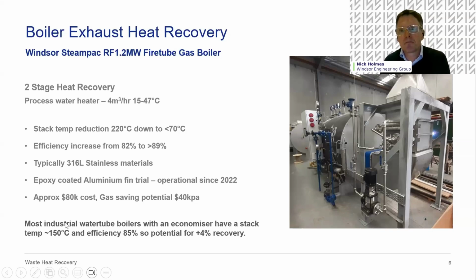So yeah, down the bottom, as Elsa mentioned earlier, most boilers have a stack temperature close to that 150. But with having an external process stream of water that can be used, you can significantly improve that efficiency by up to another 3 or 4%. It does rely on having that additional utilization, whether it's CIP water put into a storage tank. The challenges are always: what's the boiler load like compared with the external load? Will they work in sync, or do you have to have a big buffer in there to accommodate it?